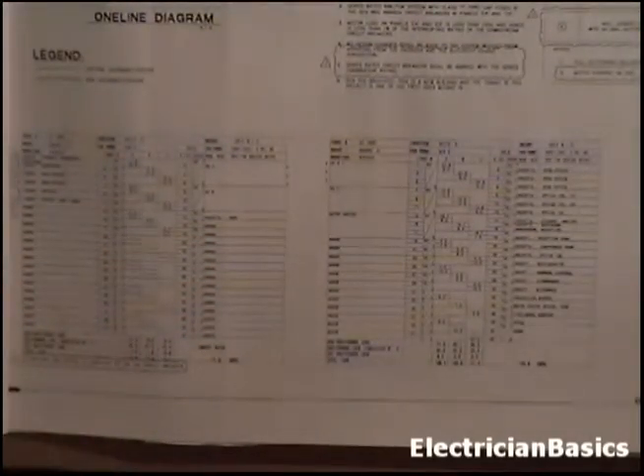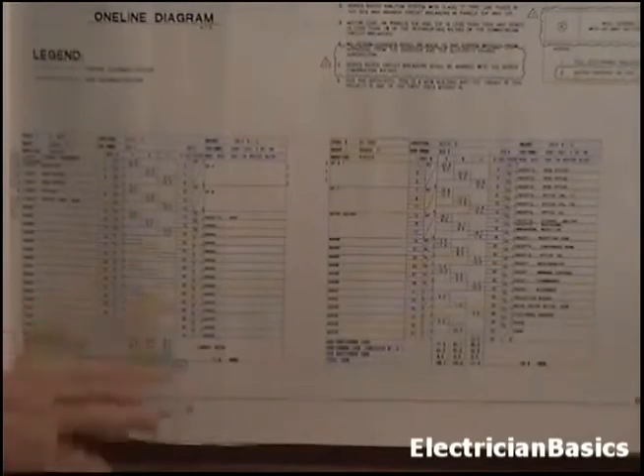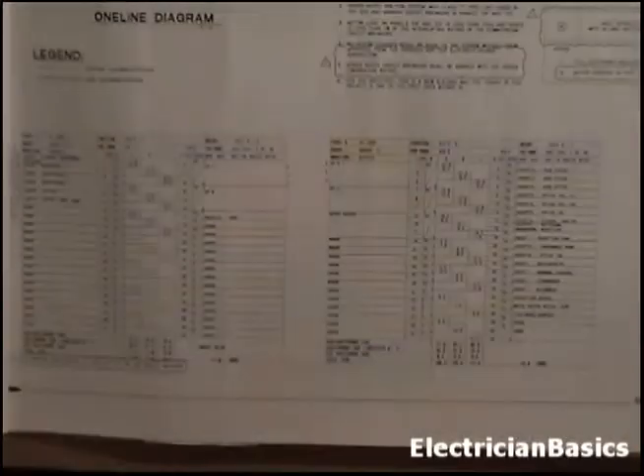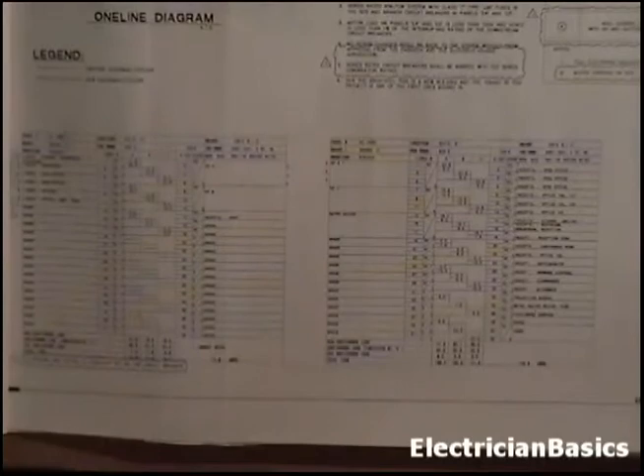These panels are nowhere near their maximum capacity, so if the tenant decides that they need to have a few more circuits added in, they have a lot of extra capacity to do that. And of course that's what the architect and the electrical engineer will do. They will make sure that the panels are big enough to allow for reasonable expansion and reasonable add-ons that a unit of this type might use. Now you can look at a unit of this type. Somebody could put a small restaurant in there. So imagine all of the cooking equipment and electrical equipment that would take. We already saw that the range took 40 amps in that kitchen. You'd have multiple ranges and maybe 2 hot water heaters and other things. And you might even have 3 panels if that was your situation.